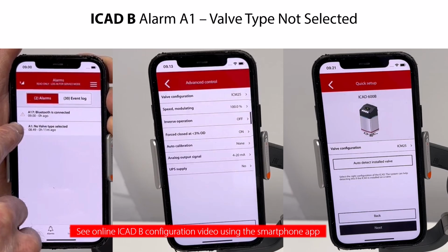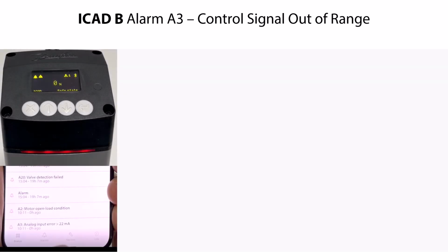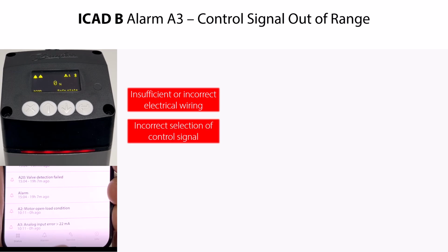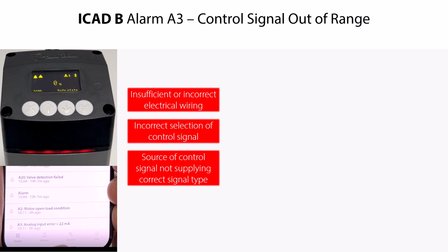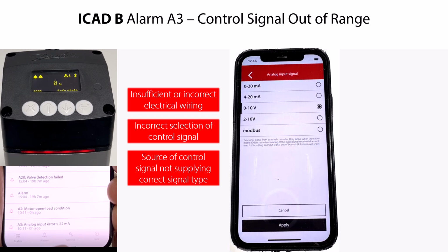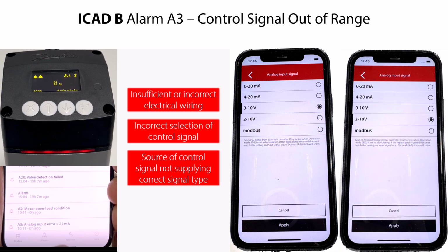The ICAD B alarm A3 is triggered if the control signal is out of the range of the selected values. The most common causes of this problem are insufficient or incorrect electrical wiring, incorrect selection of control signal, or that the source of the control signal is not supplying the correct type of signal. It is important to pay attention to the stability of an analog signal. If, for example, 0 to 10 volt is used, then we recommend to use 2 to 10 volt instead to avoid the low-end voltage with highest risk of interference.